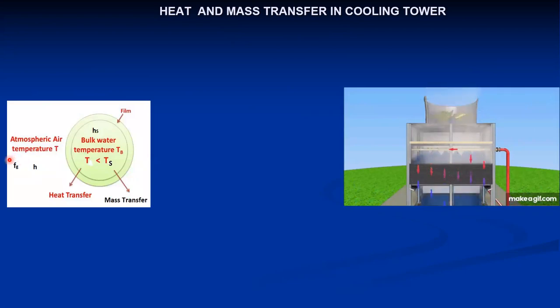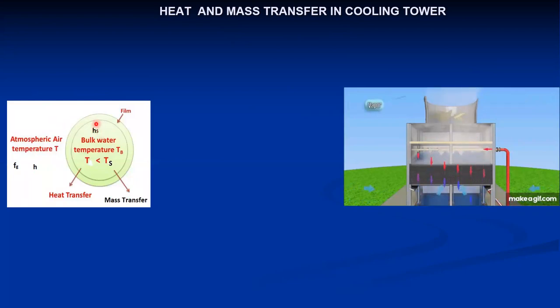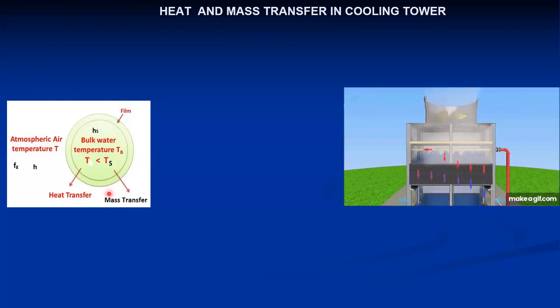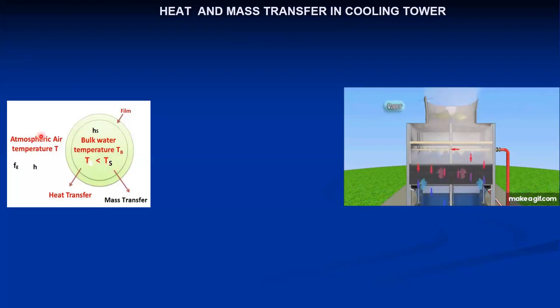Fg is the mass transfer coefficient of the air. H is the enthalpy of unsaturated air, and Hs is the enthalpy of saturated air — meaning when the air reaches that particular temperature and becomes saturated. Hs is generally obtained with the help of the water temperature at that particular instant. Obviously in the cooling tower, water temperature TS is greater than air temperature T, so TS is also equal to TW, the water temperature.